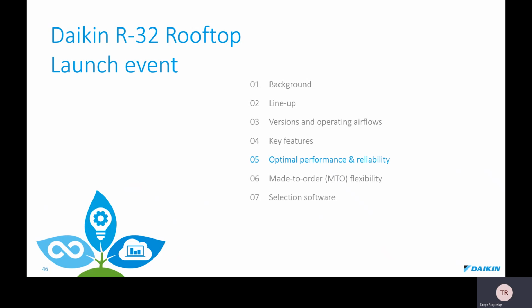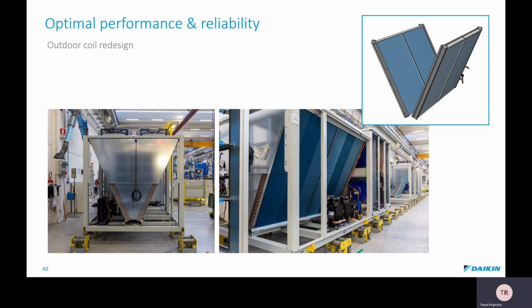Optimal performance and reliability. How do we achieve this? First of all, the outdoor heat exchanger was completely redesigned. It is now a V-shape design, which helps in achieving higher efficiencies. The coil also has hydrophilic coating for better water evacuation, which is especially useful during defrost. We have an integrated drain pan with heater to evacuate ice water and avoid unwanted ice formation in the drain pan. Here you can see a rendering of the full V-shaped coil present in the larger units, and some images of the units produced in the factory.